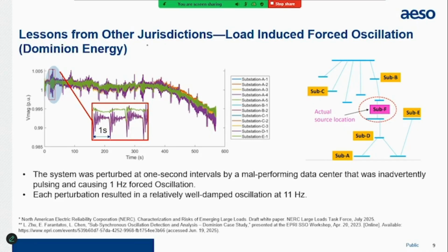The two key takeaways from this event: first, we need sufficient visibility from the grid to identify this type of event. If we didn't have sufficient PMUs in the system, we wouldn't be able to locate where these oscillations are coming from. The other takeaway is that we need to ensure these forced oscillations are limited and not causing any stability risk to the system.